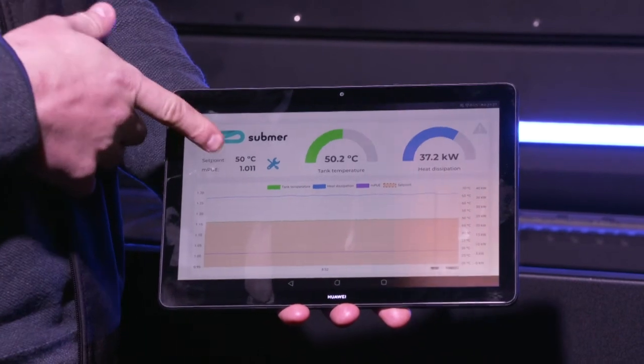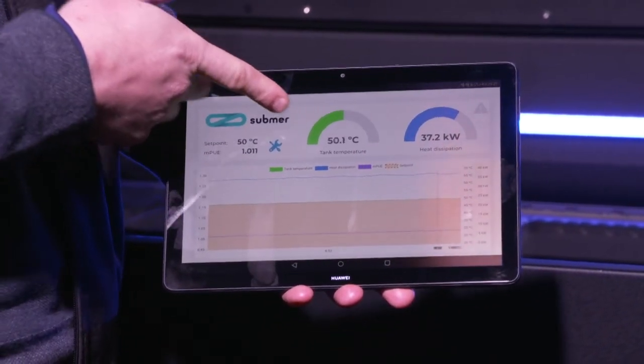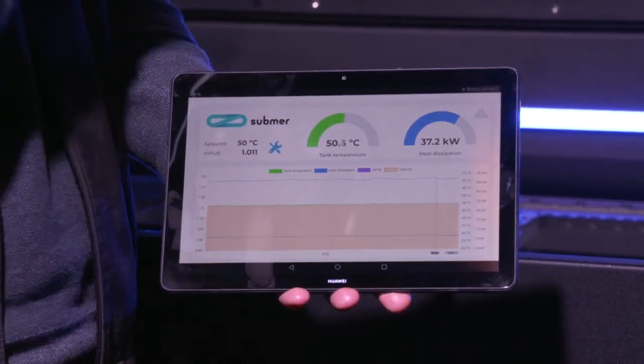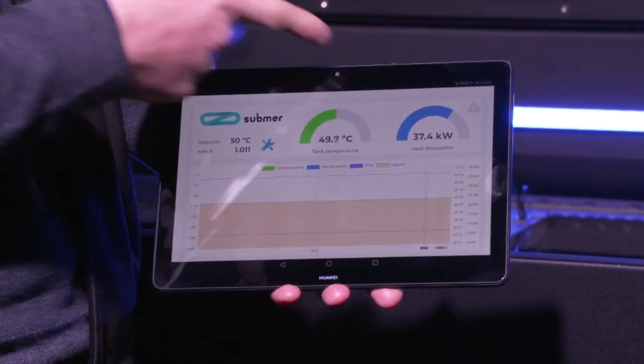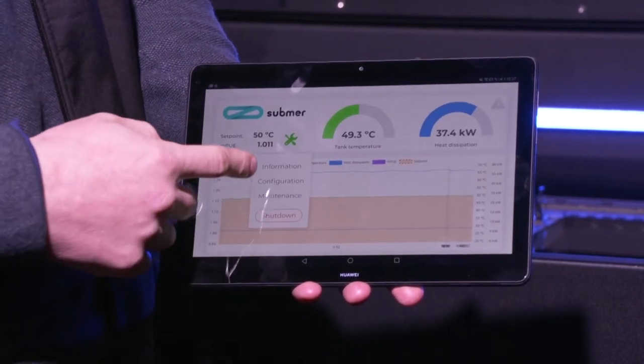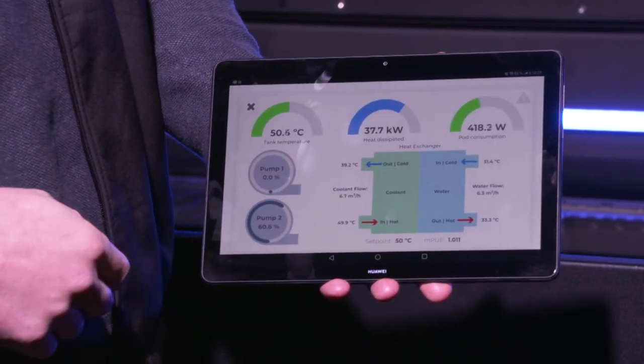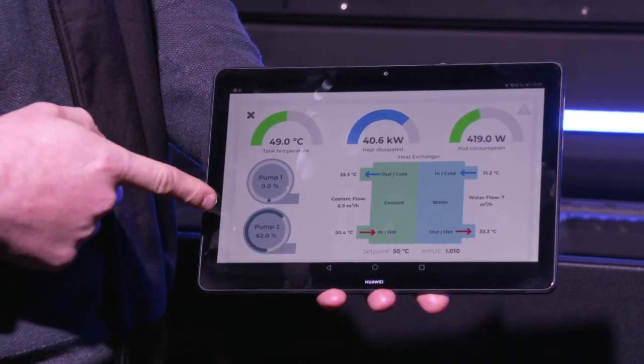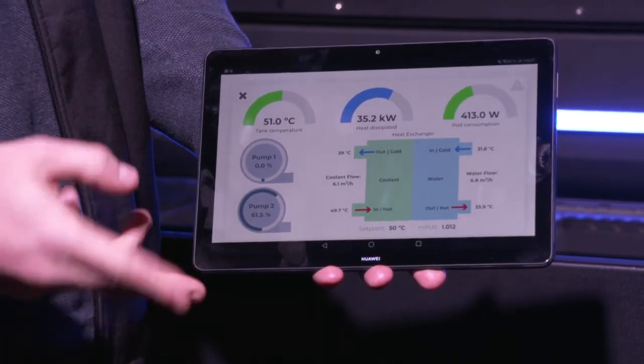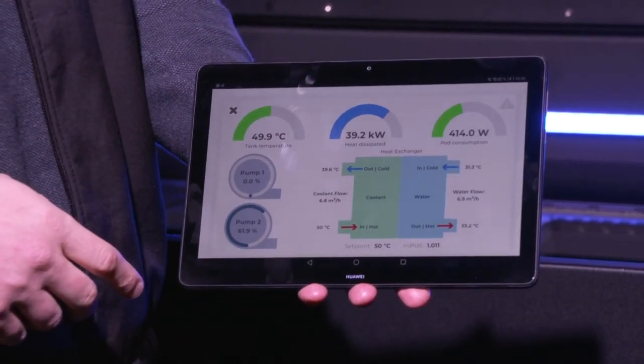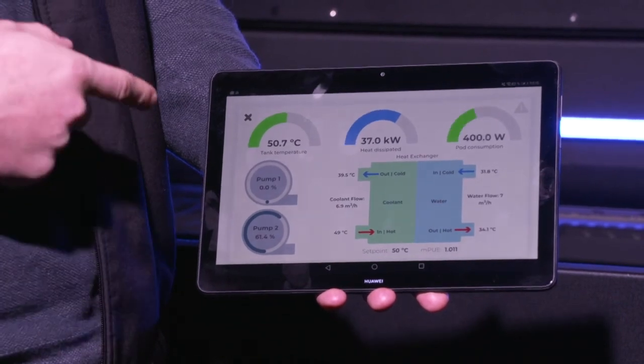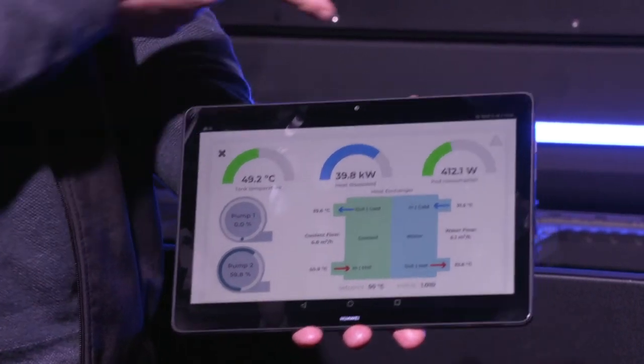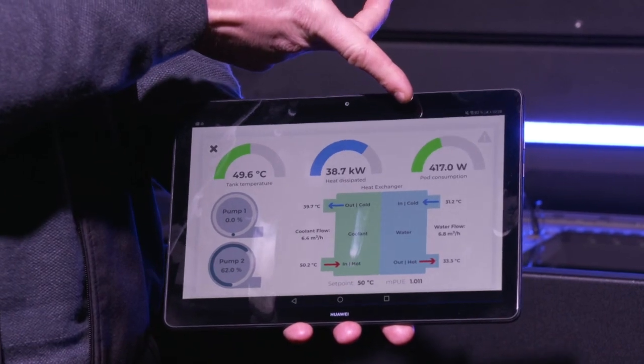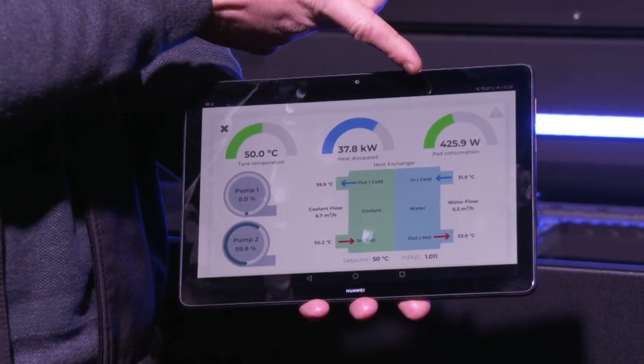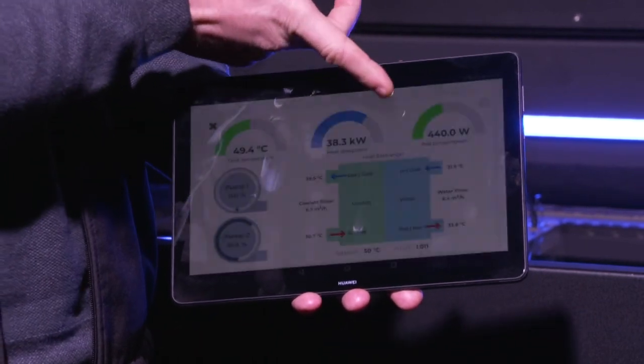So the set point temperature, the mechanical PUE of the system, the temperature at which the fluid is at the very top of the system, the heat dissipation capabilities, and then you can obviously dig into more detailed information of how the pumps are performing. The two pumps, as I mentioned, switch over every day to guarantee that the operation is resilient and that the pumps are operating correctly. Interestingly, also the amount of power consumption for the CDU, that's where we get our mechanical PUE, that super exciting mechanical PUE.